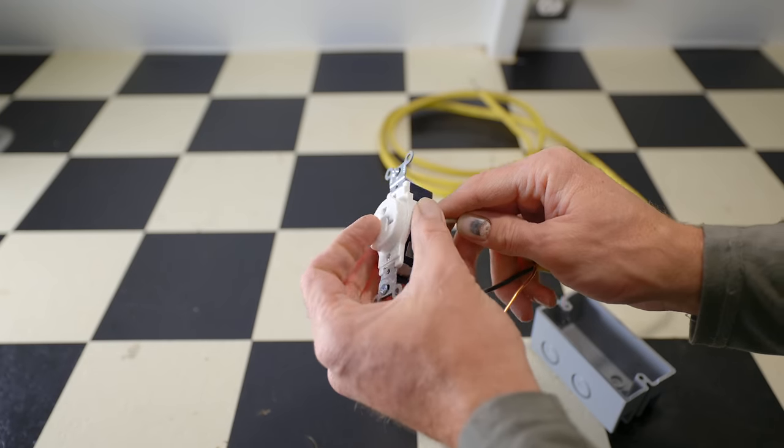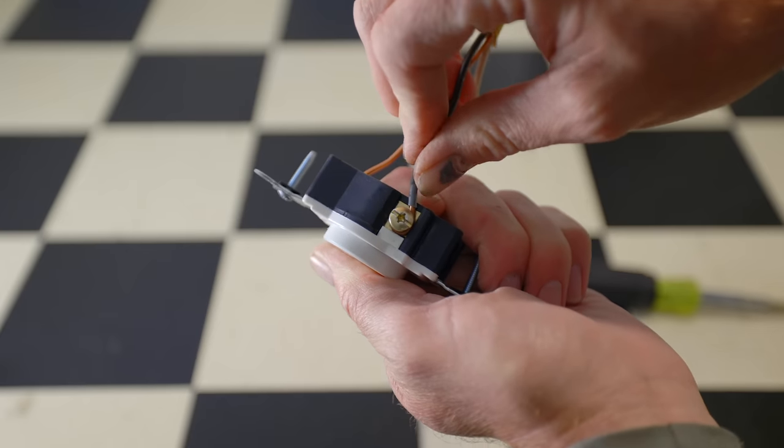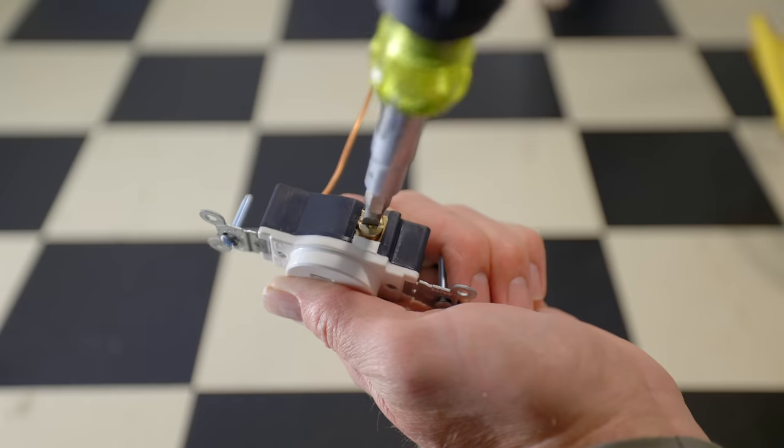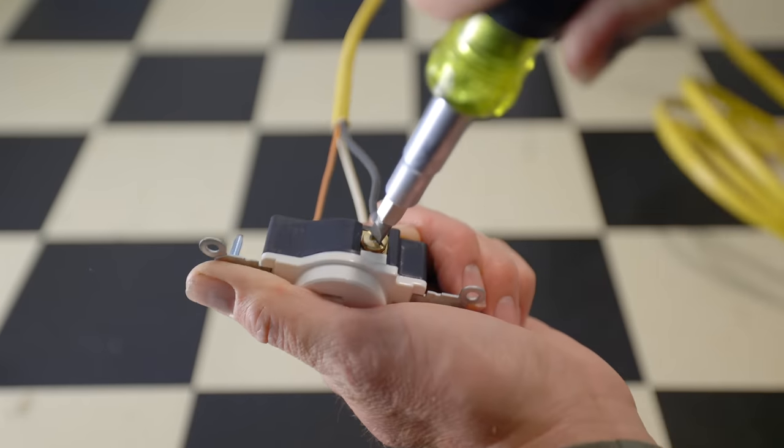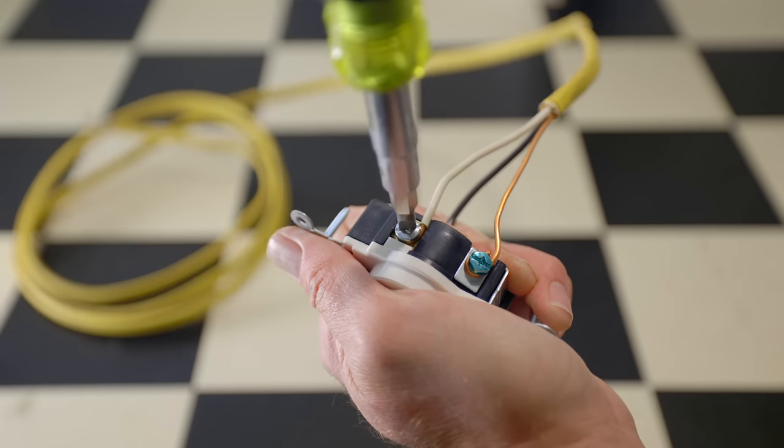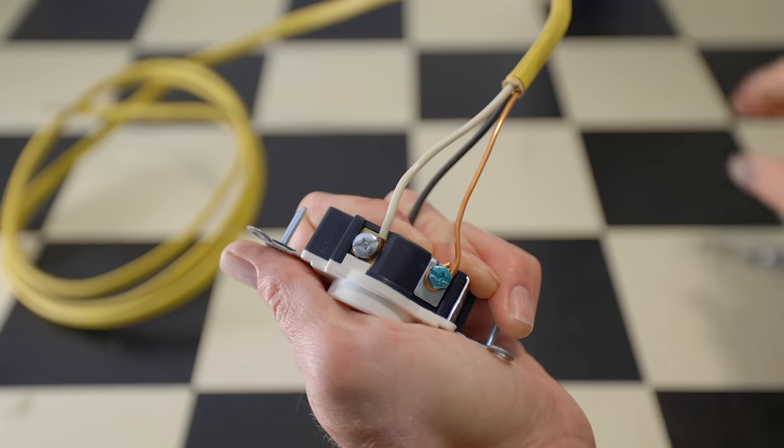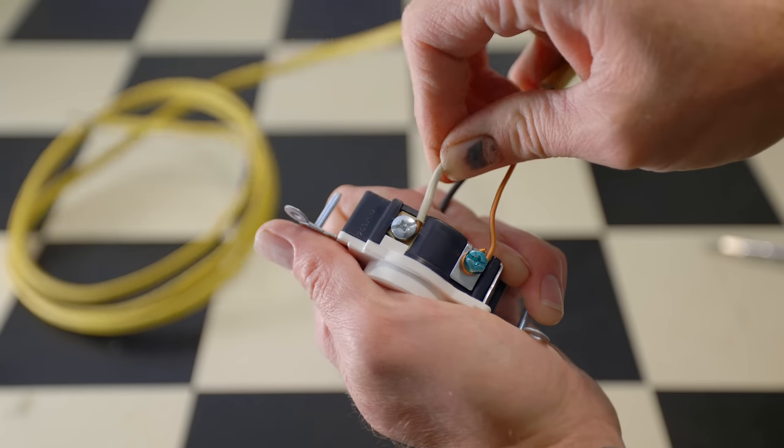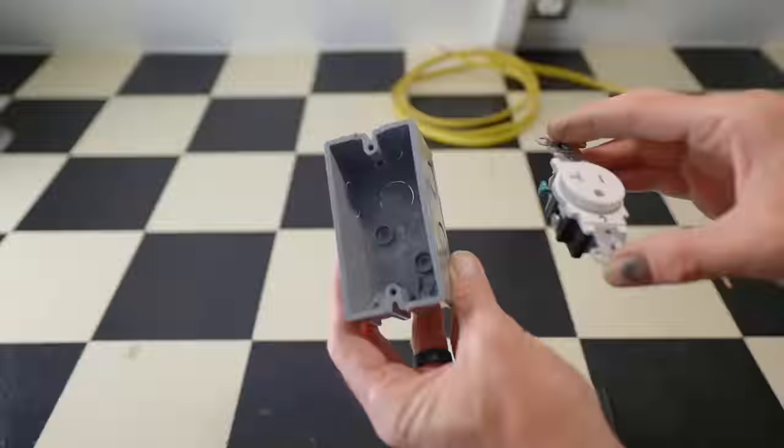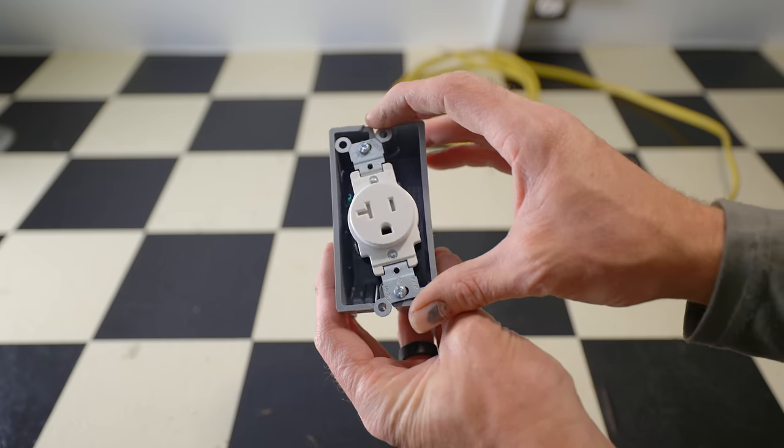If you look at the outlet that we replaced it with, and you look at the back connections, rather than it being a punch down, you can see that we can have a solid connection on there. We can torque down these screws, have a much broader connection than just that punch down. So it's a much better system.